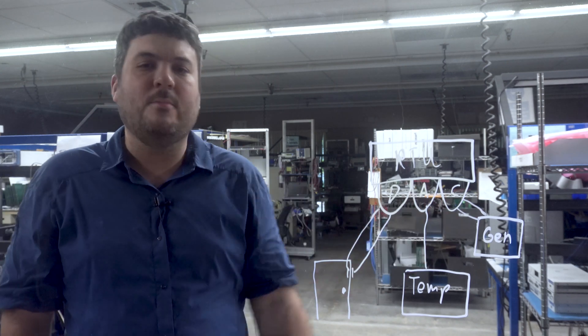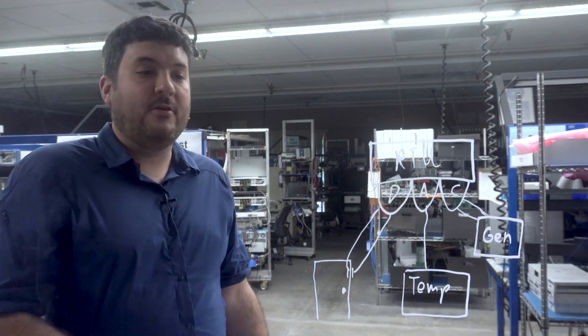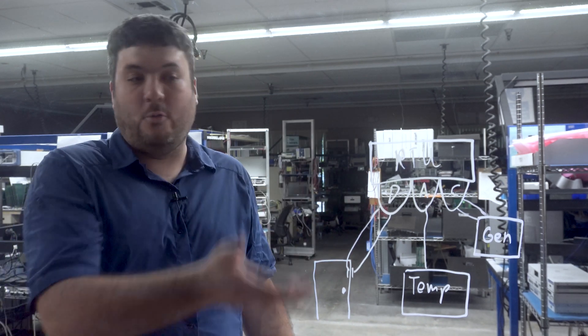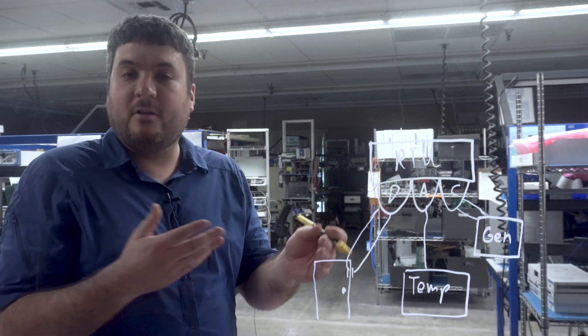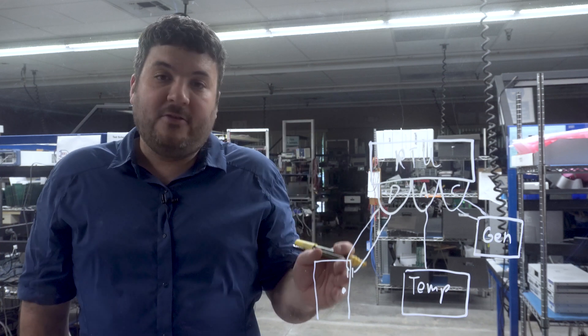So those are your big three inputs and outputs. And at this point, your RTU has a fair amount of information. Your RTU, for example, a medium-sized device might have 16 discretes and 4 analogs and maybe 4 control relays. So you'll choose an RTU that has the right combination of these. And now it has information, but it's got to get it to you somehow.